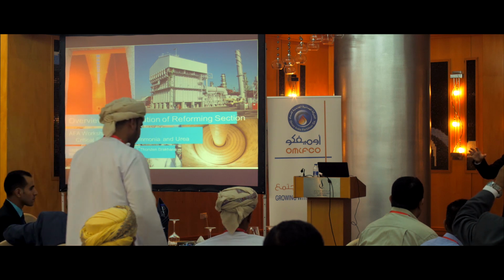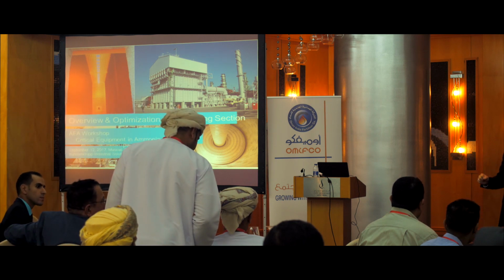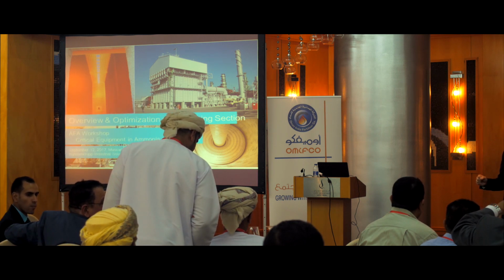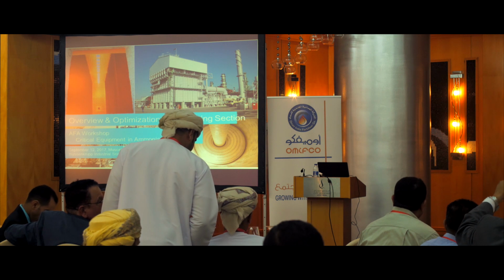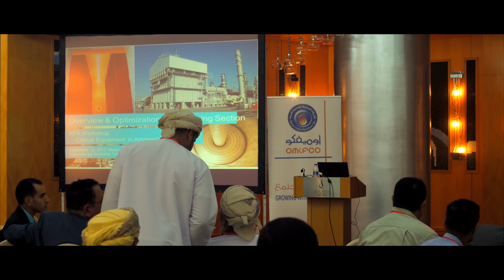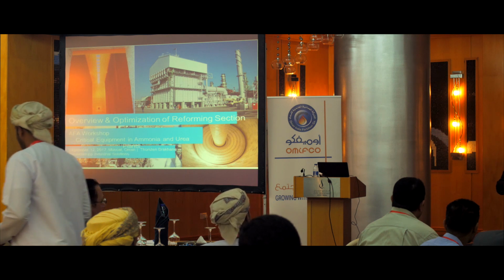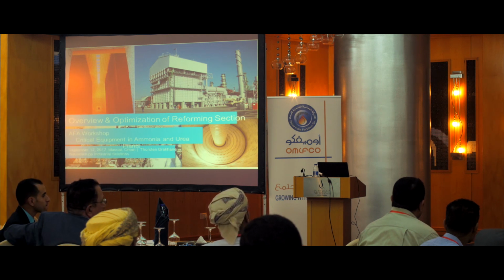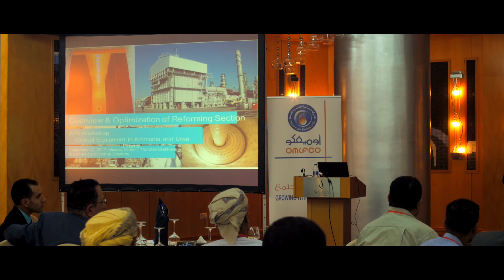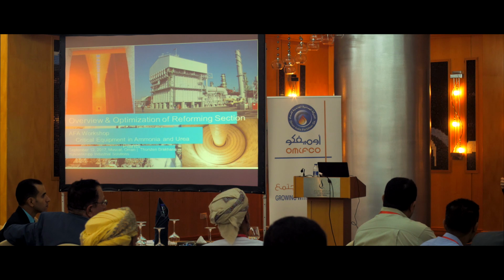Inside the skid or inside? Yes, inside. You inject ammonia through pipes, right? We have several long pipes hanging inside the convection bank, and all the pipes have small nozzles, maybe 4 or 5 millimeters in diameter. In these nozzles we inject the flue gas, which is diluting the ammonia.